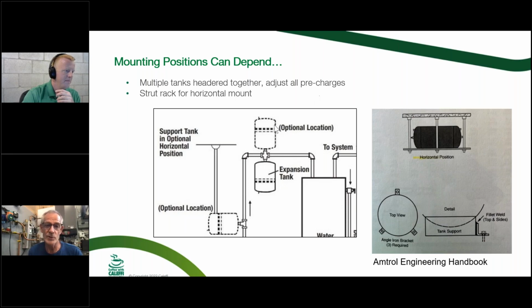Now what you're going to do there is you're going to trap some warm, moist air above that diaphragm, and maybe that tank doesn't last as long. I've seen them both that way and on their side, like on the left there, for 15, 20 years, and I don't have any example that they don't last as long or anything else. So if you mount it anyway, but especially on its side, make sure that you support it.